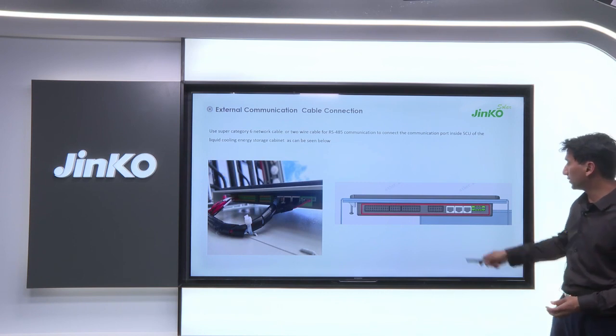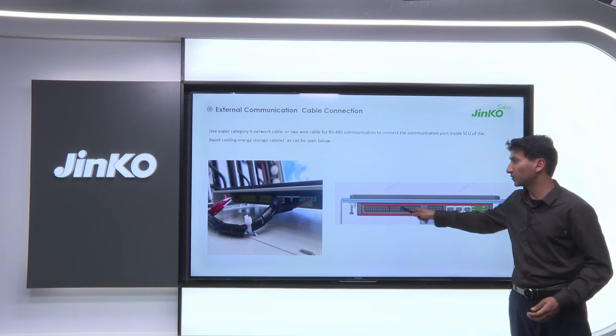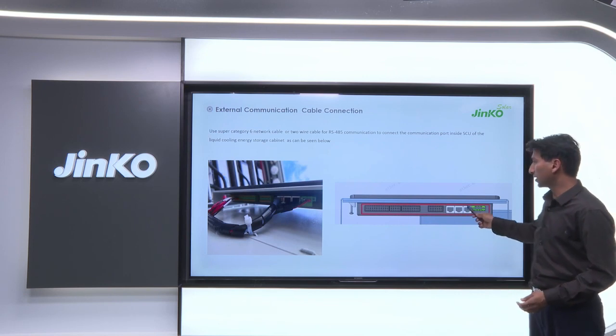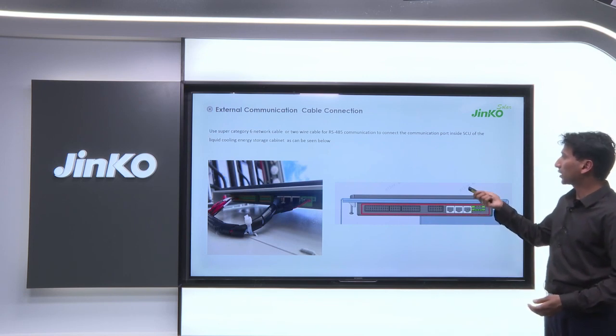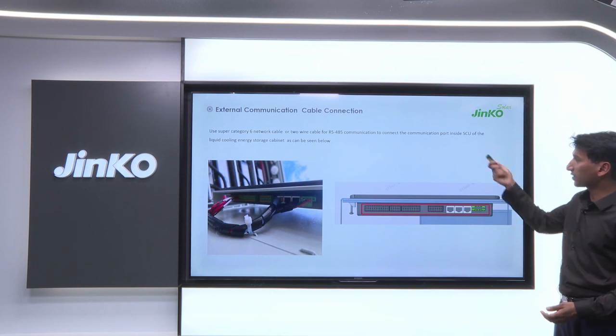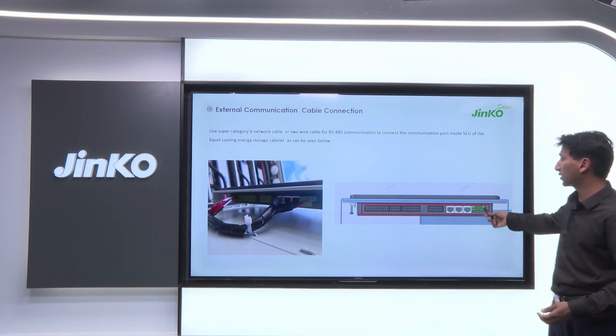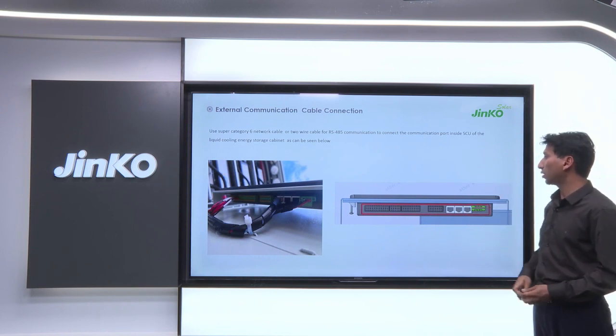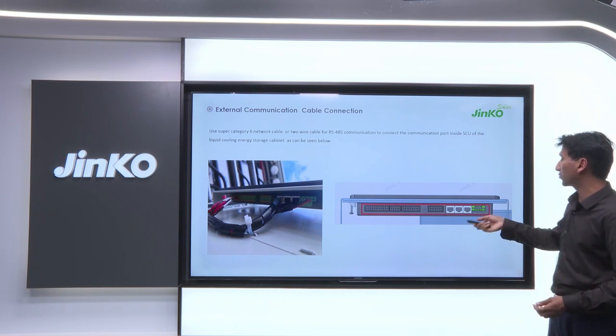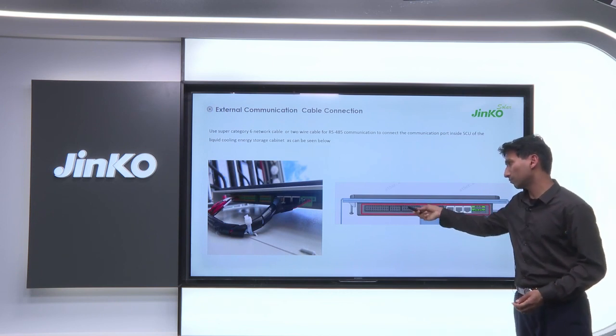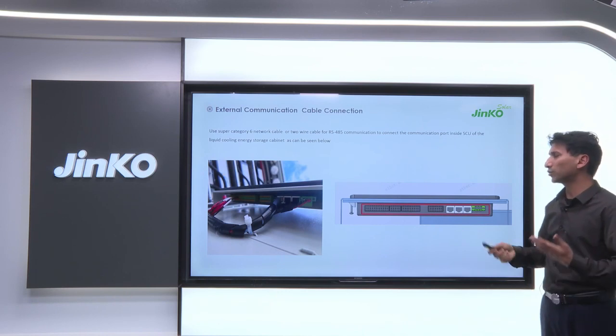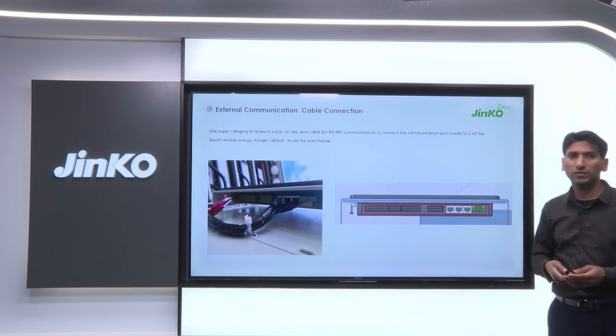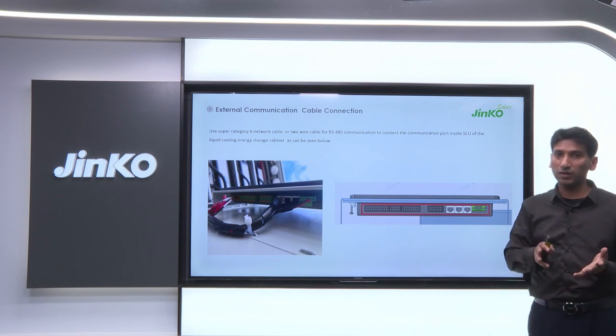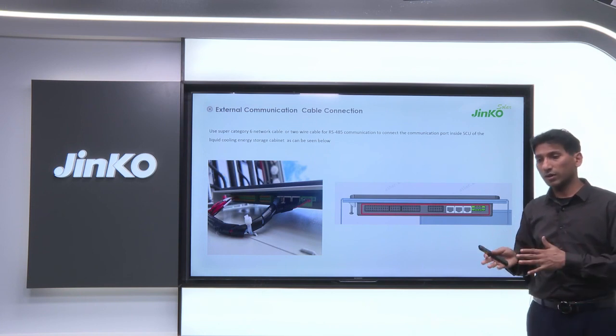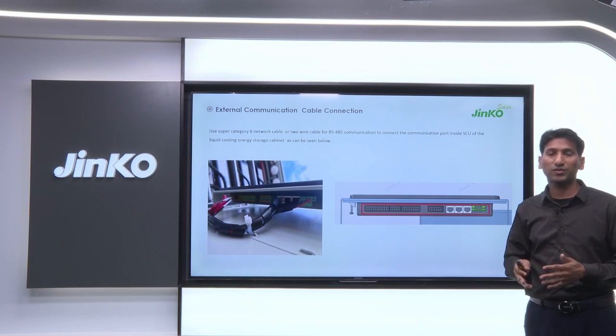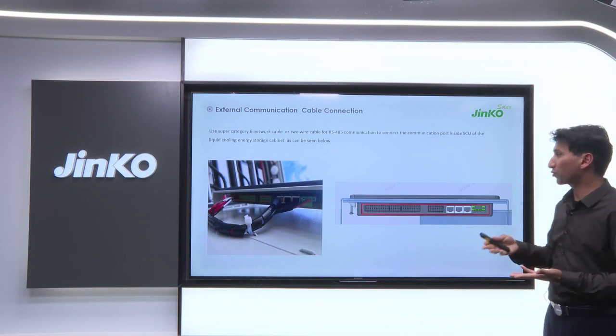The ports are here at the bottom of the SCU. This is for RS-485 communication, and this is the LAN port. You can use Cat6 cable for connecting to the LAN port, or you can connect the RS-485 communication to any of these points. It depends on your device. This has to be confirmed with us first. If you have any device, talk with our solution engineers, and we will tell you where and how to connect it.